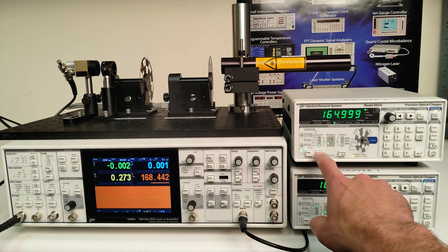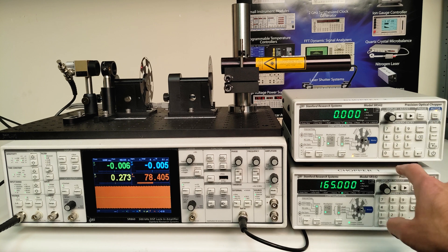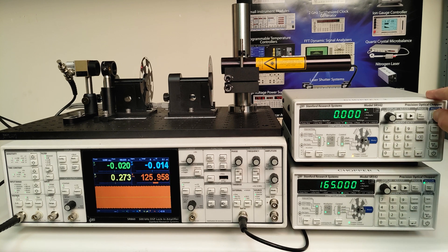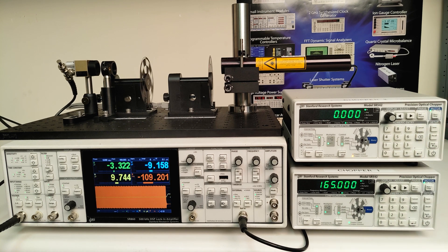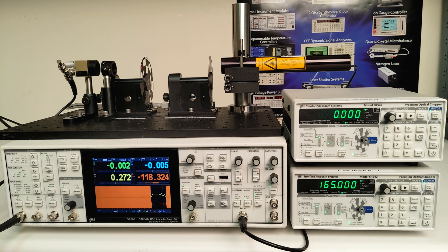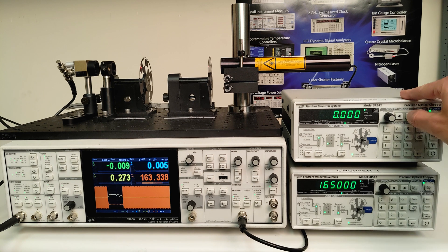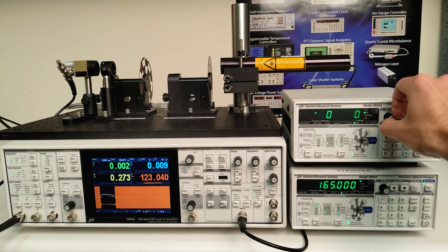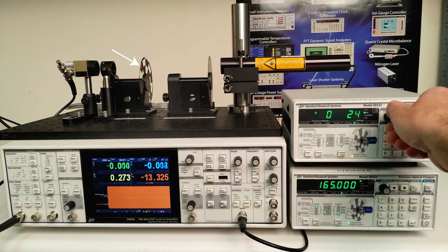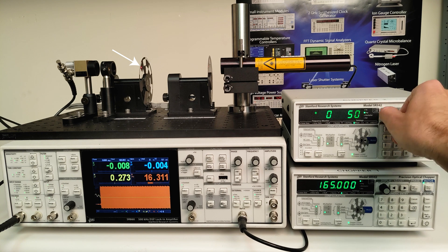To do so, set chopper 1's source to internal with a frequency setpoint of 0 Hz. When we start the motor, the motor orientation is indexed and then held at a fixed orientation of 0 degrees.